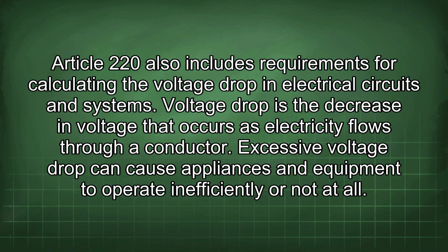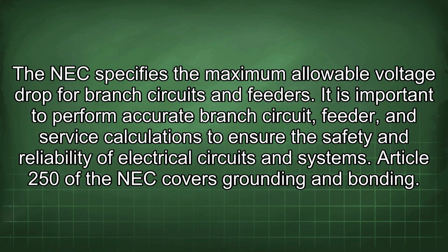Voltage drop is the decrease in voltage that occurs as electricity flows through a conductor. Excessive voltage drop can cause appliances and equipment to operate inefficiently or not at all. The NEC specifies the maximum allowable voltage drop for branch circuits and feeders. It is important to perform accurate branch circuit, feeder, and service calculations to ensure the safety and reliability of electrical circuits and systems. Article 250 of the NEC covers grounding and bonding.